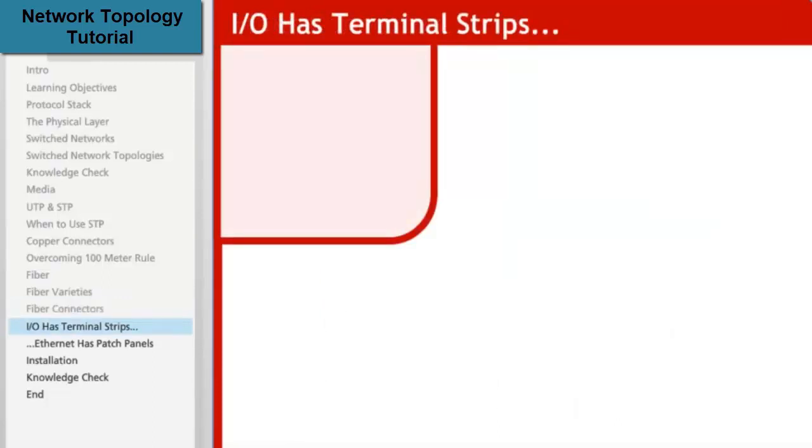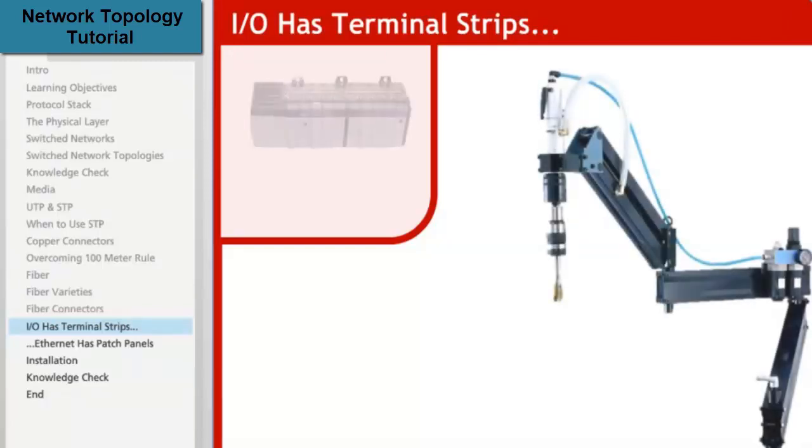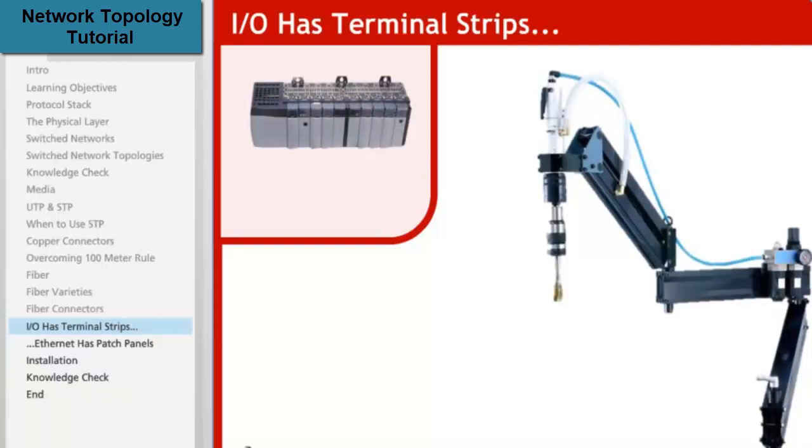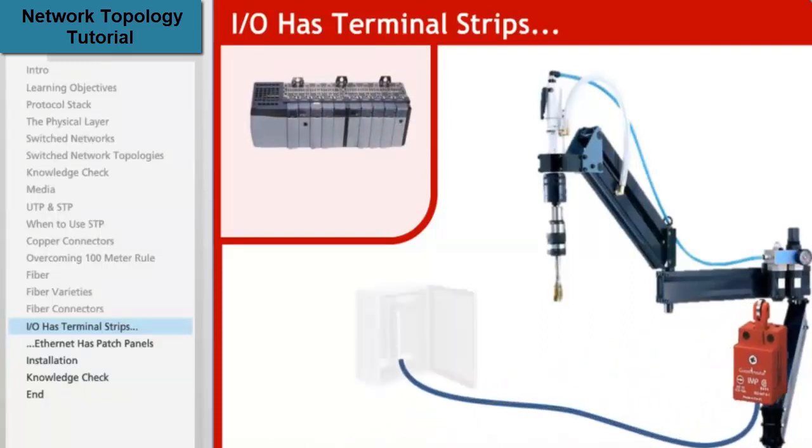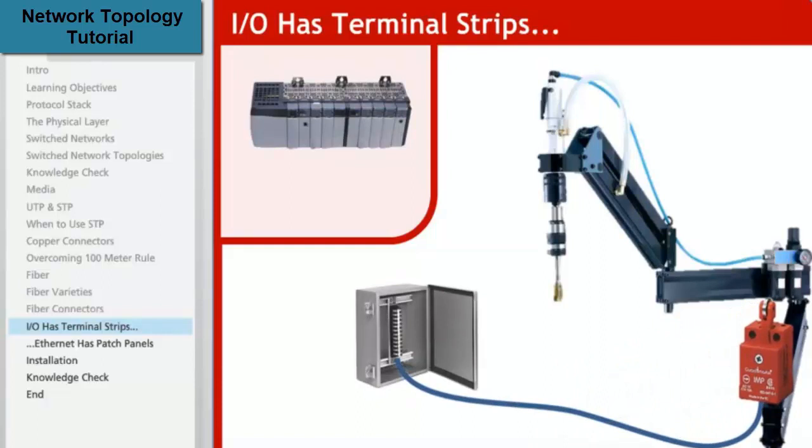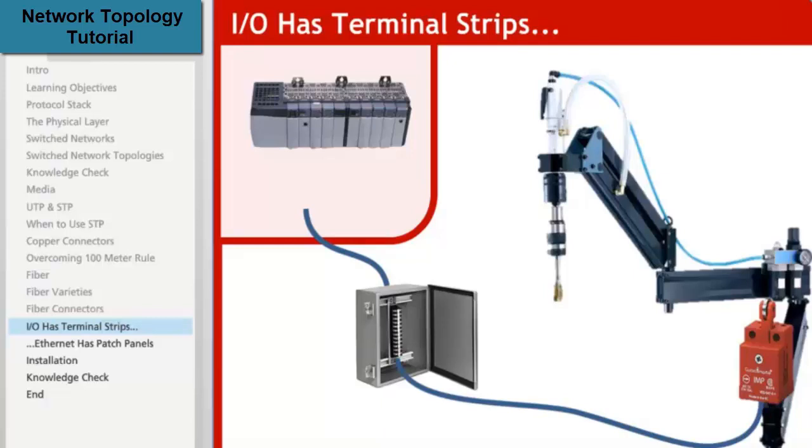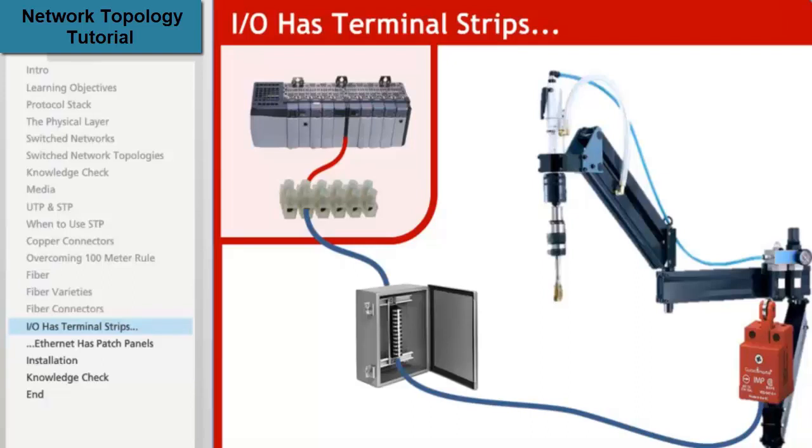A single physical channel of either fiber or copper can be made up of multiple cables, connectors, and other devices. This is similar to the way field devices are connected to the I/O of an automation controller. A limit switch mounted on a machine is connected using a length of cable to a junction box with terminal strips where other field devices are also connected. Then wire is run between that junction box and the main panel where the controller and I/O are mounted. The wires from the field device J box are landed on terminal strips. The in-cabinet interposing terminal strip is then connected to the I/O modules. If the cabinet is built and tested by an OEM or integrator, the field connections can be made to the incoming field devices and the I/O module wiring does not have to be disturbed.